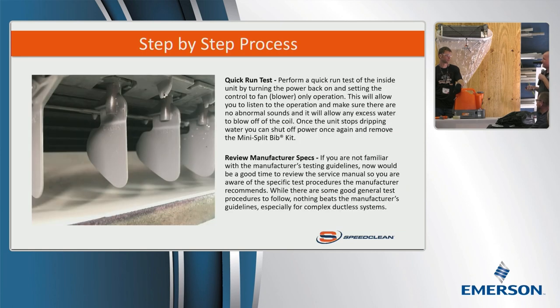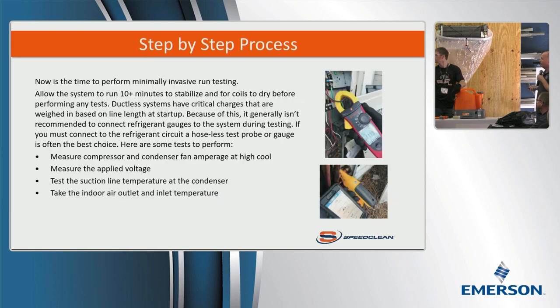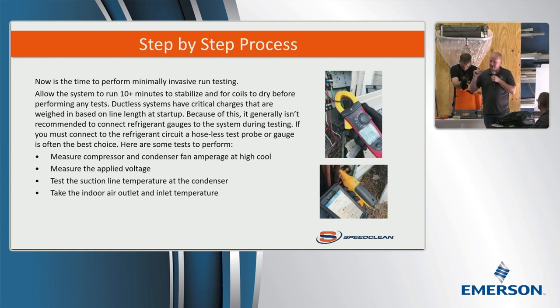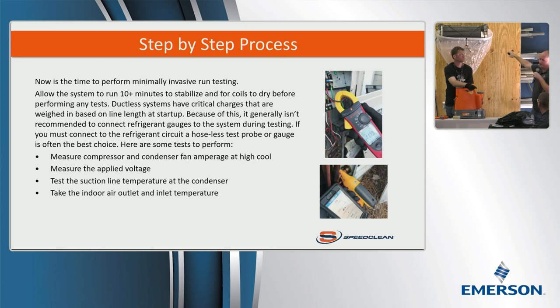Inspect the full system. I'm getting to a point here. Then once you get to the end, do your run test. And your run test, this is one of the more challenging parts: if you've just washed your evaporator coil with this kit, you need to run that thing before you take the bib off. So that needs to be part of your process.